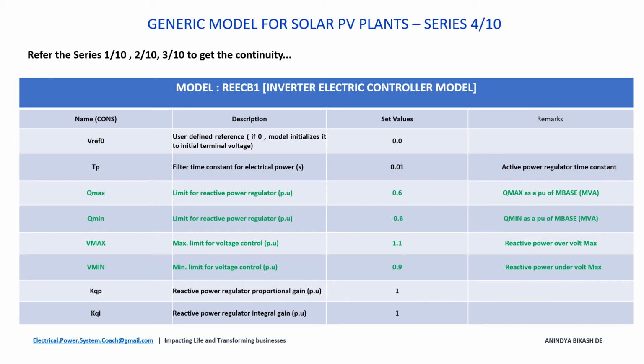The next other parameters for this REECB1, that is inverter electrical controller model, you have to set the various other parameters like the Qmax, Qmin, Vmax and Vmin. Qmax is the limit for reactive power regulator, and Qmax you have to set based on the total plant MVA base. Suppose your plant is 50 megawatt, and your base MVA is 55 or 52 MVA, whatever it is based on the calculation. So in that case, you can select Qmax is equal to 0.6 per unit on MVA base.